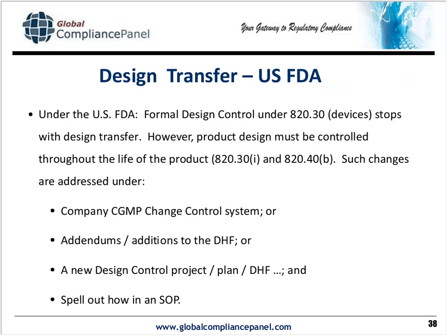Now, the design transfer, we pretty well talked about that, but we remember the issues that I mentioned earlier. So how do you define design transfer versus closing out the design history file or not closing out the design history file? Certainly, you want to determine, do I want to handle changes to the design under my GMP change control system and close out my design history file, or do I want to keep the design history file open and add design changes to it and not use the formal change control system of the GMP system?